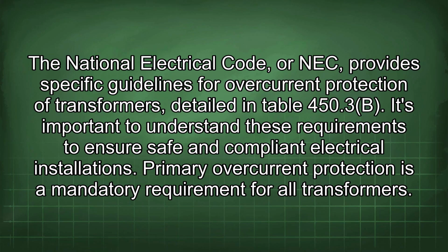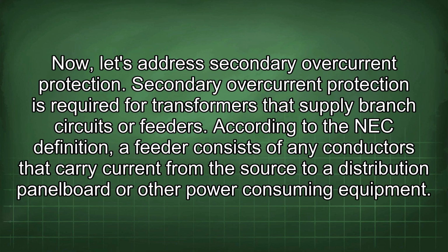The National Electrical Code, or NEC, provides specific guidelines for overcurrent protection of transformers, detailed in Table 450.3(B). It's important to understand these requirements to ensure safe and compliant electrical installations. Primary overcurrent protection is a mandatory requirement for all transformers. Now let's address secondary overcurrent protection.